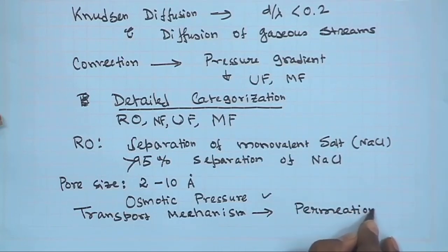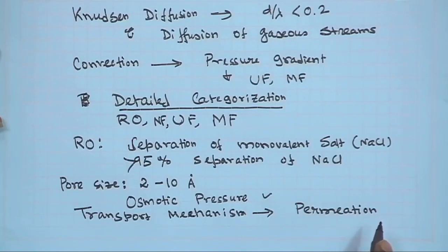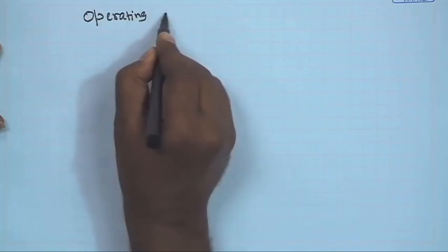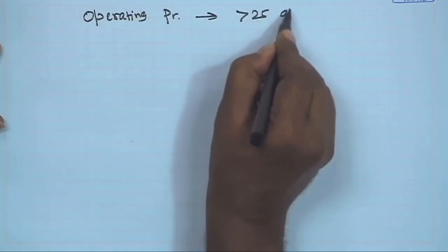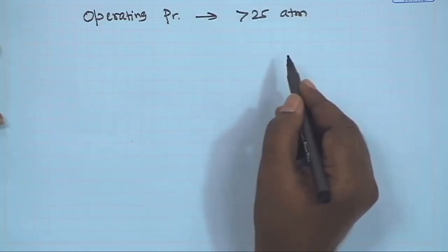The transport mechanism in reverse osmosis is permeation — dissolution, diffusion, and desorption — because we are dealing with a very small pore size. The reverse osmosis membrane is also called almost a non-porous membrane. The throughput depends on the operating pressure range. Typical operating pressure will be above 25 atmospheres; most desalination plants operate around 50 to 60 atmospheres to overcome the osmotic pressure of the solution. The effective driving force is the operating pressure minus the osmotic pressure — the greater this difference, the higher the throughput.